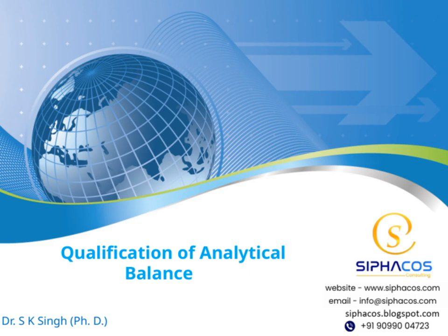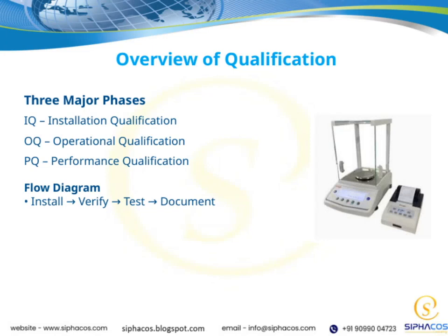Let's get started. Now, let's look at the three major phases involved in qualification. First, we have IQ, which stands for Installation Qualification. This phase ensures that all equipment and systems are installed correctly and according to specifications. Next is OQ, or Operational Qualification, where we verify that the equipment operates as intended under normal conditions. Finally, we have PQ, or Performance Qualification, which confirms that the system performs effectively and consistently in real-world conditions.